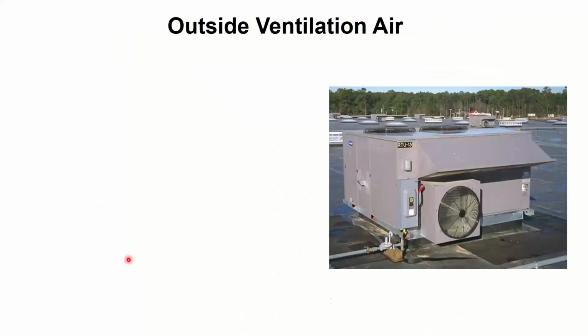So how do we get that fresh air in there? You guys are going to have all sorts of different types of equipment, and we'll touch on those. But just generically speaking right now, let's assume you have packaged rooftops on top of your building, right? Here's a packaged rooftop unit. It's a box that does your furnace, your air conditioner, all the blower fans, the condenser fans, everything's in one box. And there is usually an outside air intake hood on here. If there's not, you need to get one. So this guy allows fresh air to suck up underneath here and mix in with the return air from the space and then be heated, cooled, filtered, etc., and delivered back to the space, right?